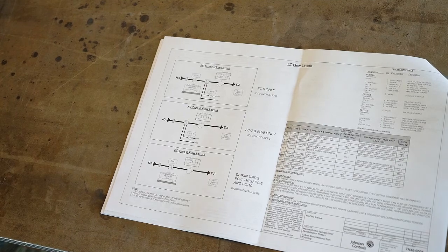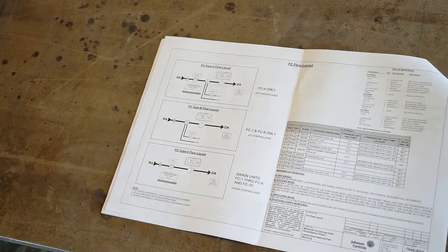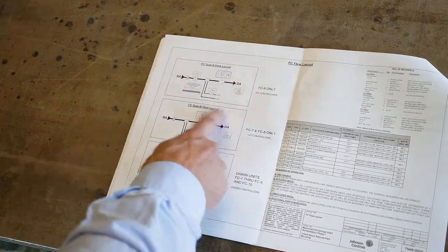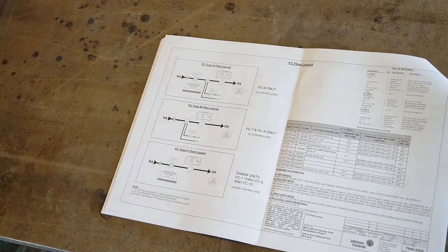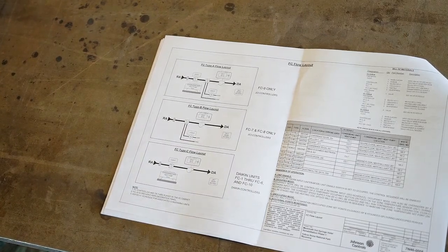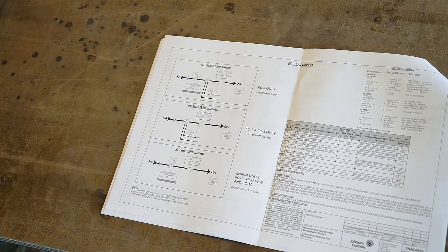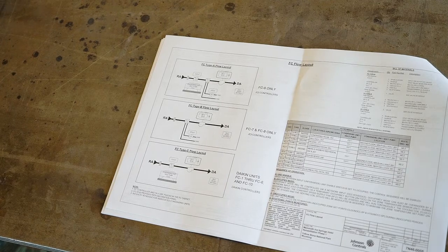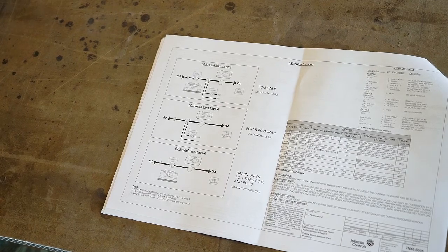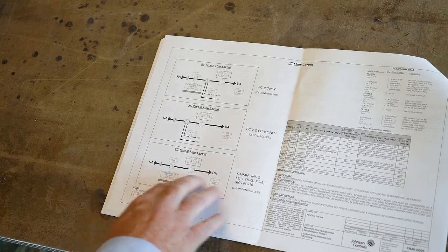Okay, fan coil 8 does the map room, fan coil 7 does the gift, or let me rephrase that, fan coil 9 does the gift shop, fan coil 7 does the main entry, and fan coil 8 does the map room again. Okay, they're little bit different setups, and that's why their different drawings are on here. So fan coil 9, which does the gift shop, has heating and cooling both on it to cool that area. Fan coils 7 and 8, which do the main lobby once you get into the building and the map room, have heating only. Okay, and basically the Daikin units have cooling only on them at this point in time.